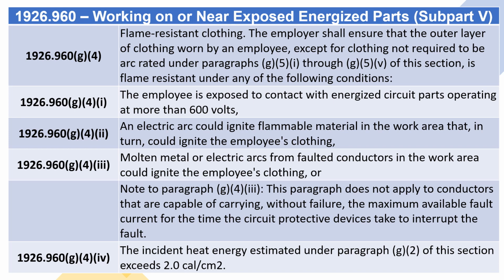1926.960(g)(4) Flame-resistant clothing. The employer shall ensure that the outer layer of clothing worn by an employee, except for clothing not required to be arc-rated under paragraphs (g)(5)(i) through (g)(5)(v) of this section, is flame-resistant under any of the following conditions. (g)(4)(i) through (g)(4)(iv): The employee is exposed to contact with energized circuit parts operating at more than 600 volts. An electric arc could ignite flammable material in the work area that, in turn, could ignite the employee's clothing. Molten metal or electric arcs from faulted conductors in the work area could ignite the employee's clothing. Or, note to paragraph (g)(4)(iii): This paragraph does not apply to conductors that are capable of carrying, without failure, the maximum available fault current for the time the circuit protective devices take to interrupt the fault. The incident heat energy estimated under paragraph (g)(2) of this section exceeds 2.0 calories per square centimeter.